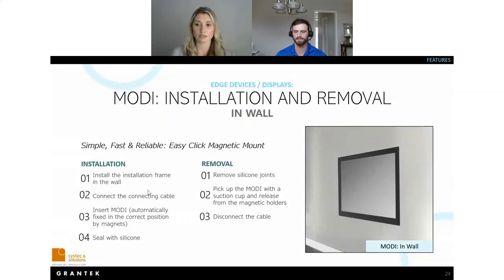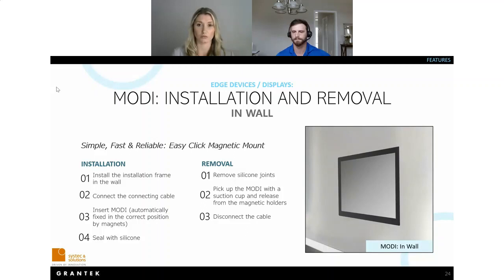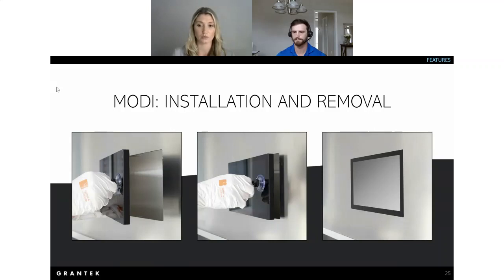The Modi can be installed two ways: in-wall or flush-mounted. Customers typically install it in-wall for new construction, though it is relatively easy to install in an existing facility as well. The installation process involves inserting the installation frame into the wall, connecting the cables, inserting the Modi, and sealing with clean room silicone. Removal is also simple: remove the silicone, use a suction cup to pick up the Modi, release from the magnet holders, and disconnect the cable. Photos show how the suction cup and magnet are used to remove and install the unit.